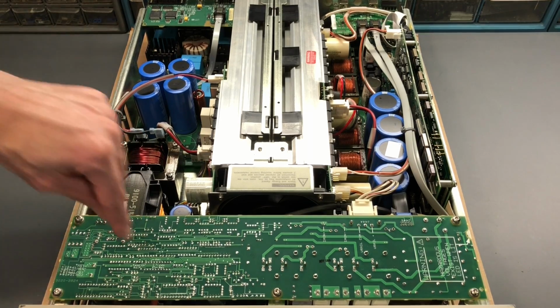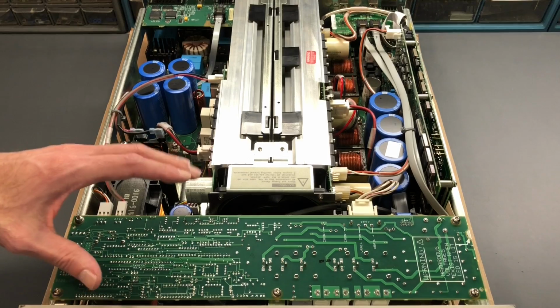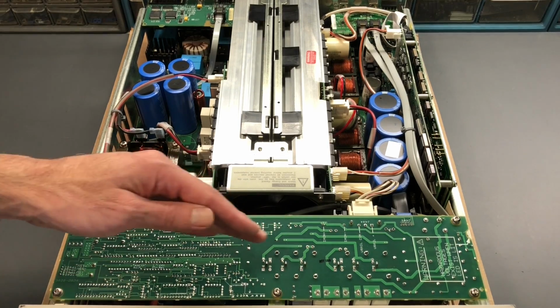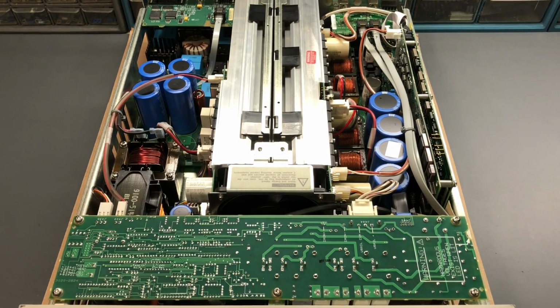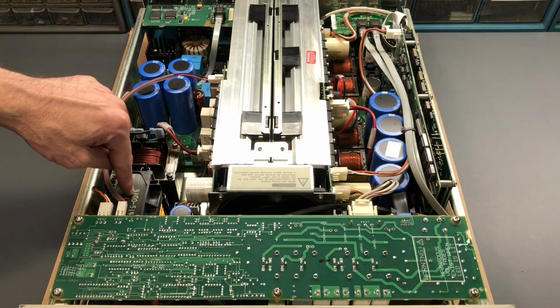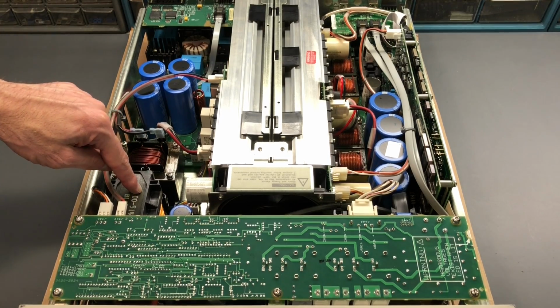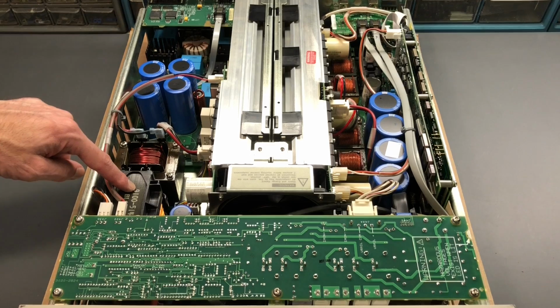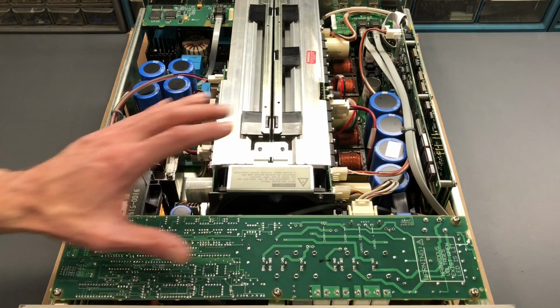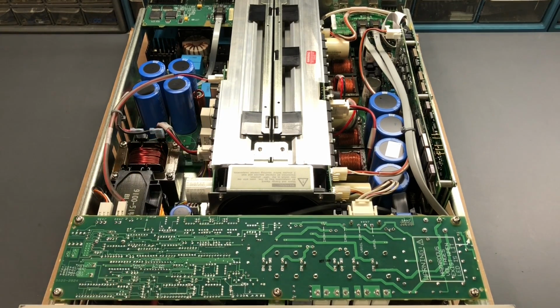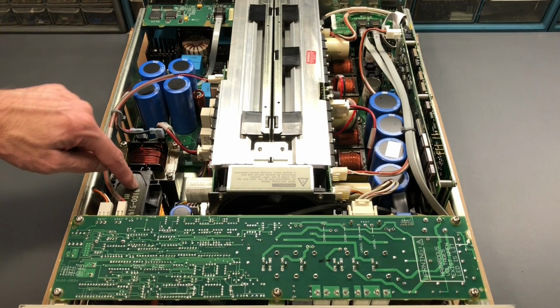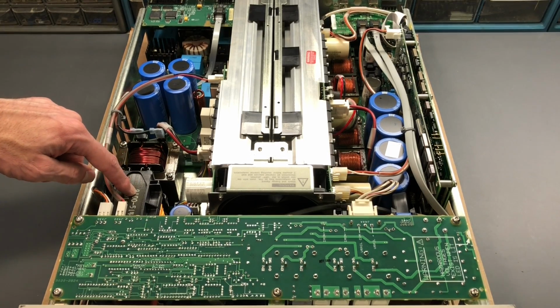The circuit board that's underneath this board, you saw previously there were some large heat sinks on some of the devices on that board. That's the bias assembly. This is also the bias transformer right here. So this is a 60 hertz transformer at this point. This is not a high frequency transformer. A lot of what happens in this AC power source is basically a switch mode design type power supply, so there's very high frequency switching going on to drive some of the transformers. But this transformer in this case is not, it's a traditional 60 hertz transformer.